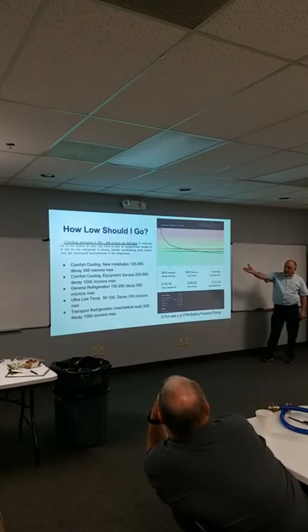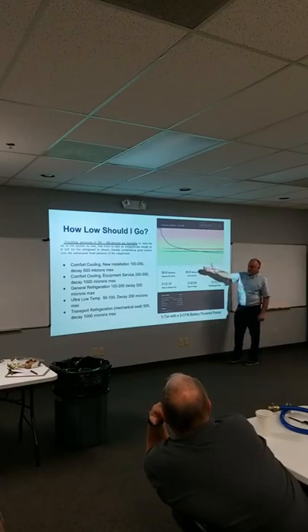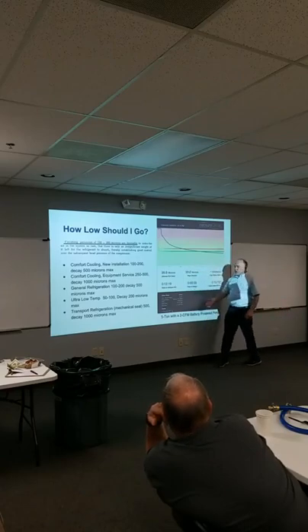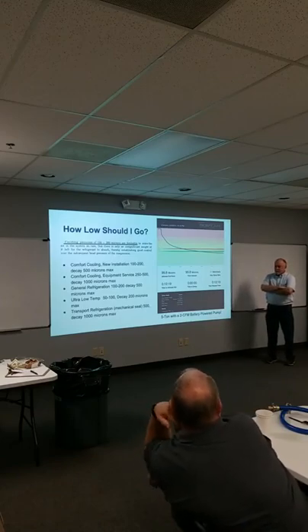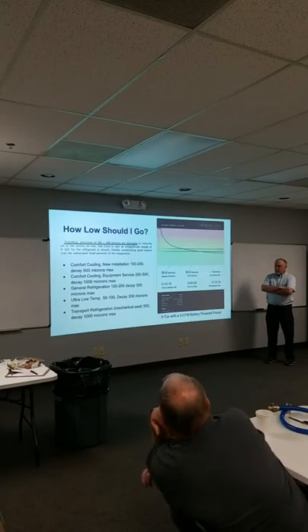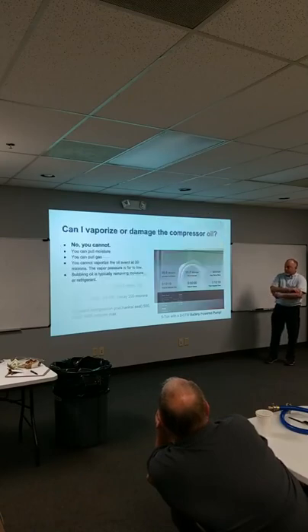For comfort cooling installations, I recommend 100 to 200 microns, 500 microns max decay. Equipment service, you're lucky to get 250 to 500 with a mineral oil. It's pretty easy. With POE, you're not going to get down much below 1,000. General refrigeration, same. They're ultra low. You guys used to do cascade systems. I know, Mark, you guys did those. Those require very low vacuums, down to 50 to 100 microns, sometimes even less, all right?